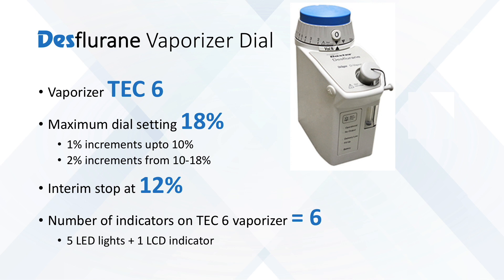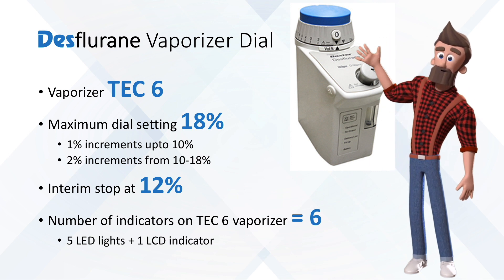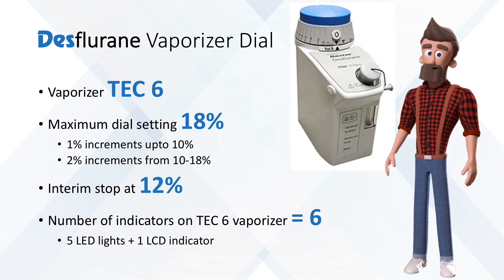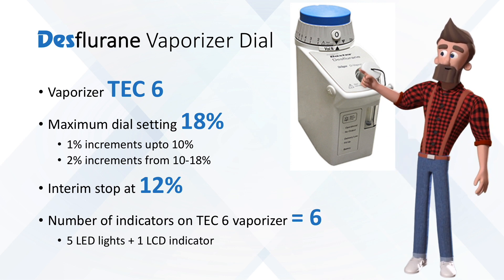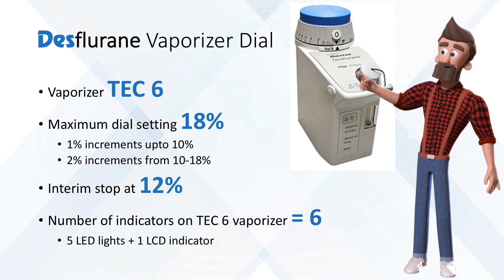Now we come to the vaporizer. The vaporizer for desflurane is the Tec 6. Looking into its features, the maximum dial setting is 18 — and 18 is 3 times 6. It also has an interim stop at 12%, and 12 is 2 times 6.